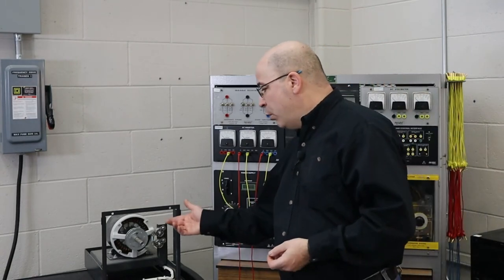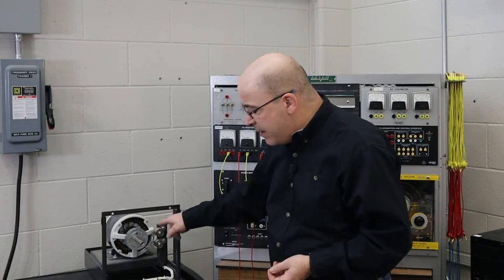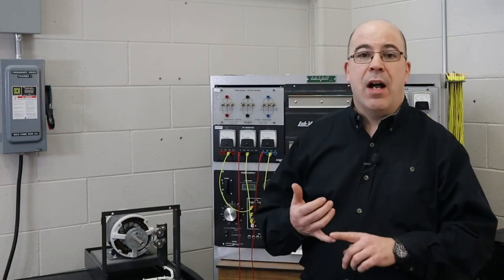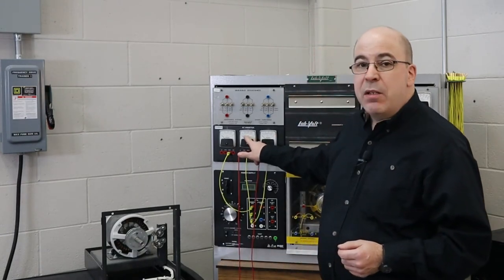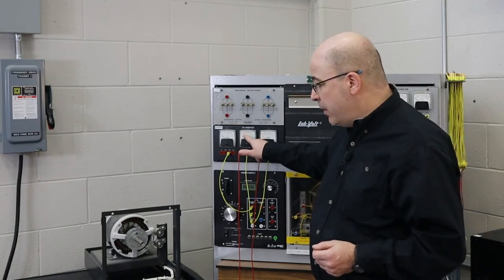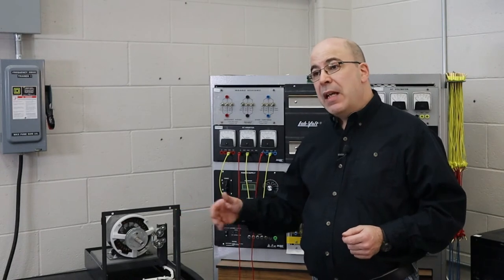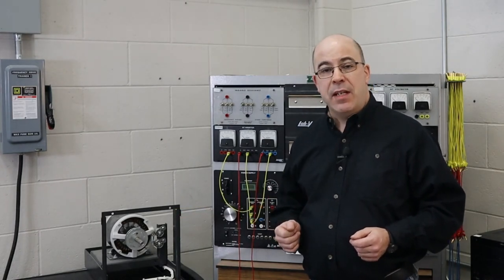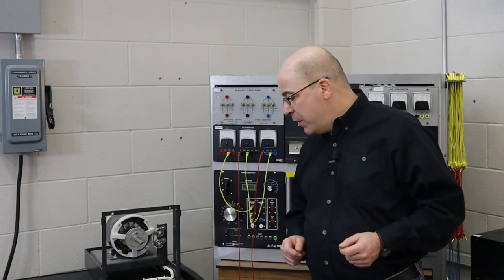If I've got too much current flowing through that's going to be bad because the windings in the motor are going to get hot and heat is the enemy when we're talking electrical equipment. If this motor was rated at no more than 1.2 amps of current and we're subjecting the motor to more current than it was rated for that's going to shorten the life of the machine and that's something we want to avoid. Now let's get back to our demonstration.